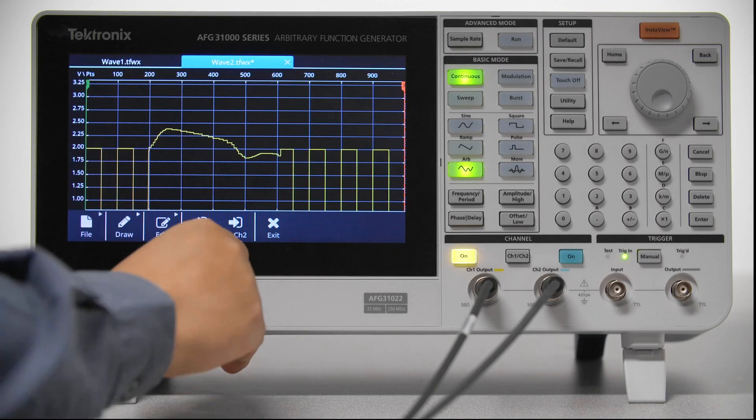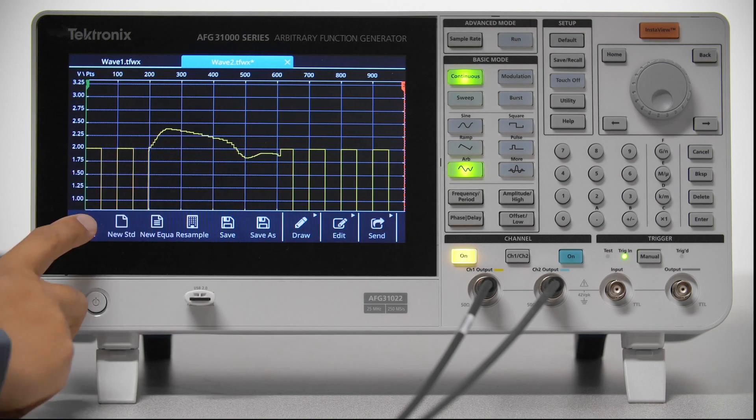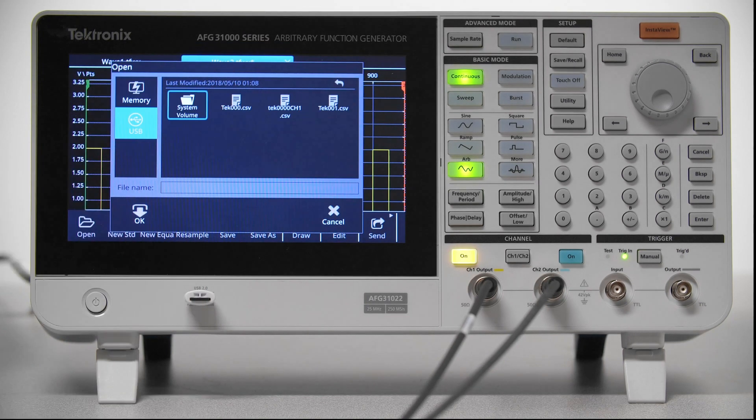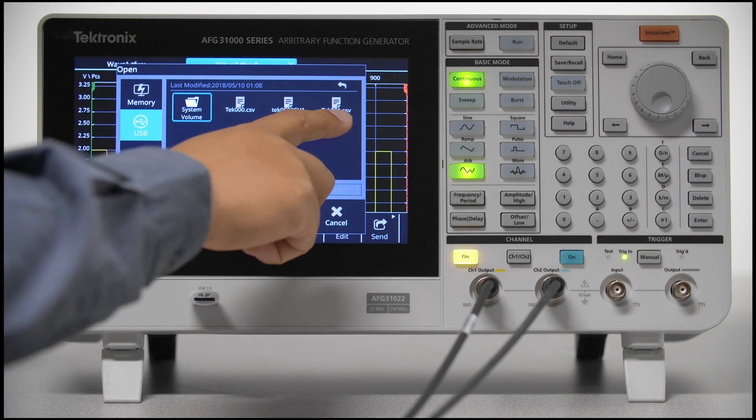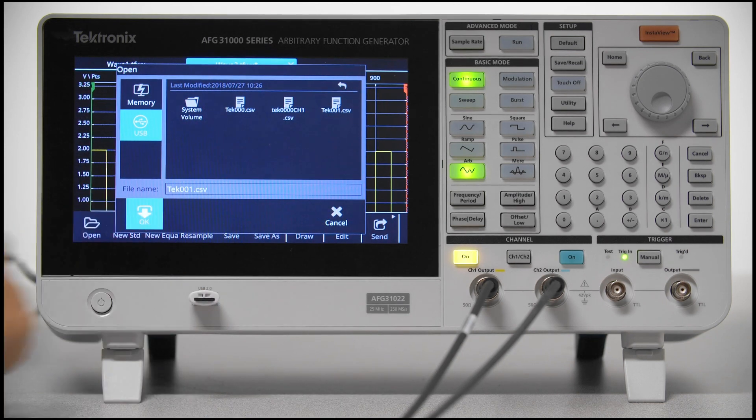We can also save the waveform from the scope and import it to the AFG using a thumb drive. Here you see the saved waveform from the scope. Just click on it and press OK and we've successfully imported the waveform.